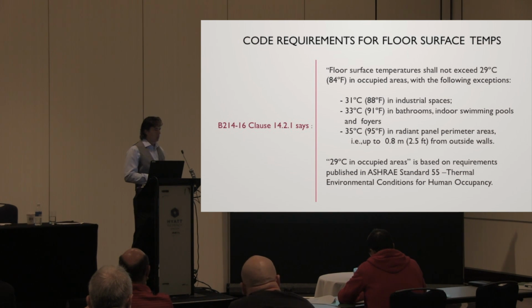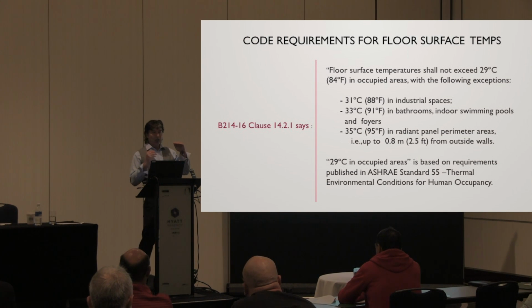I know your hardwood guys would have something to say about all of these things with respect to the temperature that they want to have their wood at. But as far as human comfort and the CSA code, and as far as we're concerned, that's our limitations for surface temperature. So you really need to calculate the thermal resistance of the material you're heating through. Just because our floor is 91, that does not mean that's our floor surface temperature. We could have a circulating water temperature of 130, so we have to calculate that in. What's our circulating temperature? What's our floor surface temperature going to be? This is all part of doing the radiant design, to understand that we're not going past our surface limitations.